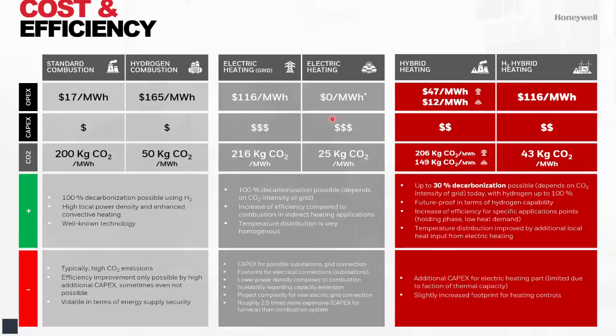And as I already mentioned, depending on the design of the system, we are hydrogen ready from the first day on, so you're not blocking this avenue by going electric. Depending on the application state, we can switch between different points of combustion, electric, or both, and with this we're able to increase efficiency. We don't need excess air anymore like we did before.